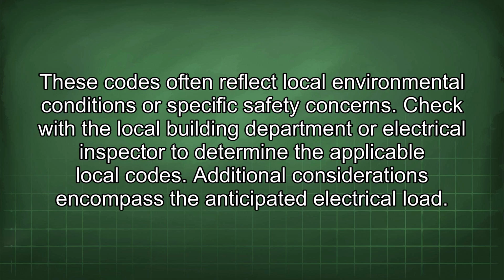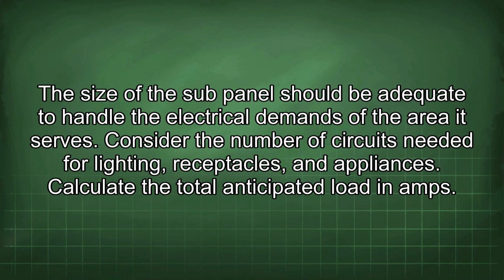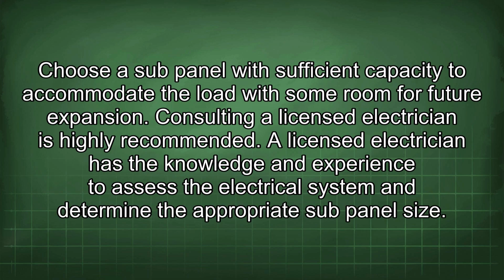Additional considerations encompass the anticipated electrical load. The size of the sub-panel should be adequate to handle the electrical demands of the area it serves. Consider the number of circuits needed for lighting, receptacles, and appliances. Calculate the total anticipated load in amps. Choose a sub-panel with sufficient capacity to accommodate the load with some room for future expansion. Consulting a licensed electrician is highly recommended.